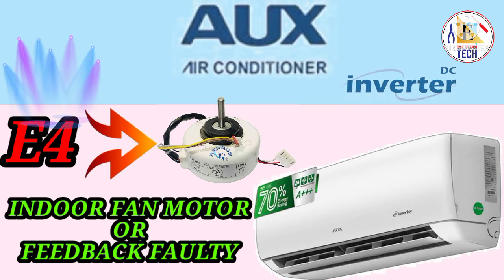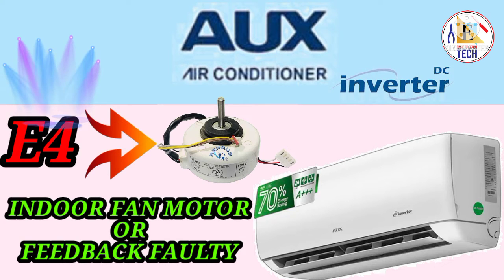Let's see the next error code. When you see E4 on your indoor display, it means your indoor fan motor is having some problem. Sometimes if your indoor motor is stuck, it shows the error. If the feedback from the indoor motor to the PCB is not received correctly, it also shows the error. At this time, there will be ice formation on your indoor coil because your fan is not working, and it will show the error E4.